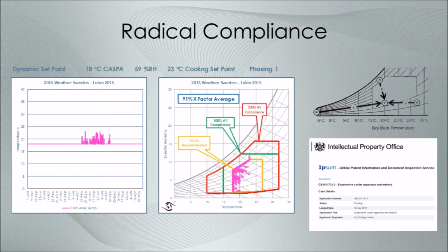We need to create compliant conditions. You're probably familiar with ASHRAE standards and things like that. In our conventional cooling systems, we're actually able to achieve almost total compliance in the northern parts of Europe with no refrigeration, no chilled water, no DX. This is potentially the way forward for lowest cost operation and simplicity. We can achieve 100% compliance with 2 mixing dampers, a fan and a filter. That then becomes achievable to manage these hyperscale operations.